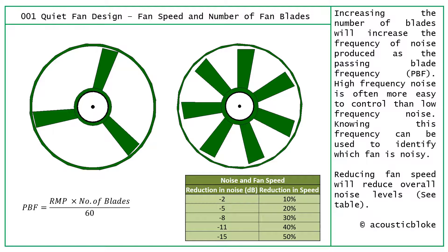The next thing we can do to control fan noise is simply to slow the fan down. The table indicates the likely reductions in noise level depending on what percentage we reduce the fan speed. For example, a 30% reduction in speed would equate to approximately an 8 dB reduction in total noise level.